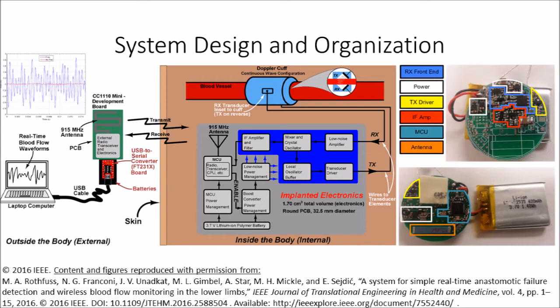The system is comprised of a battery-powered wireless implantable blood flow monitor. The external computer controls a transponder that turns on and communicates with the implanted electronics. The blood flow data wirelessly collected from the implant is displayed as a blood flow waveform for real-time viewing on the computer screen. Compared with other implantable wireless blood flow monitors, the implanted electronics in our system are the smallest reported in literature, approximately 1.7 cubic centimeters without encapsulation. A small implanted package reduces bioburden.